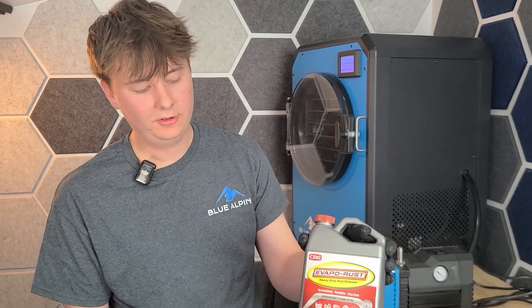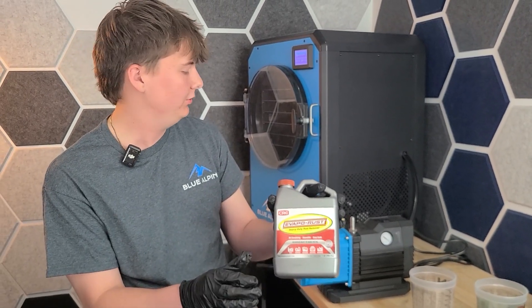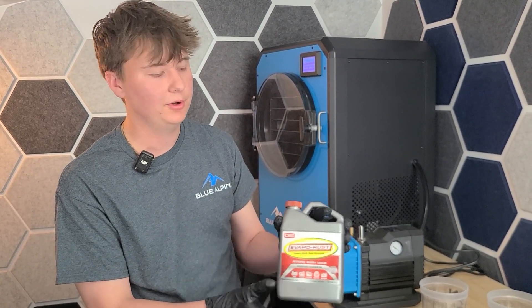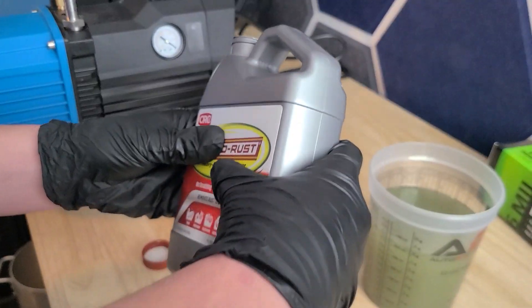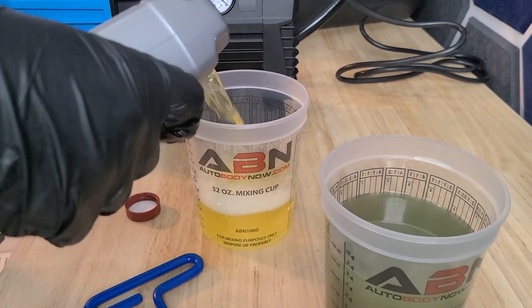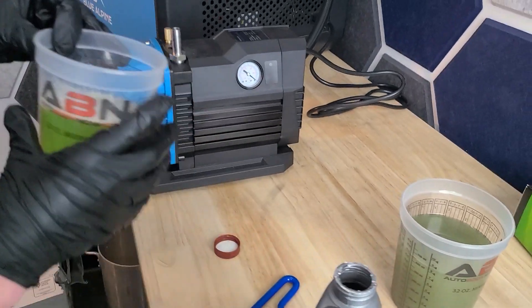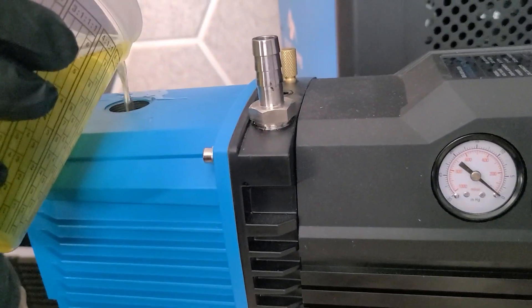So this is Evapo-Rust. This is a really good cleaner for your pump because it'll break down all the grime — it's just a heavy-duty cleaner. It will not cause damage to your vacuum pump at all if used the way we recommend. We are going to open it up and fill up our other cup to about the same amount as I would fill up with oil, so it's about 18 to 20 ounces. From here, take the Evapo-Rust and pour it into the opening just like you're pouring in the oil.